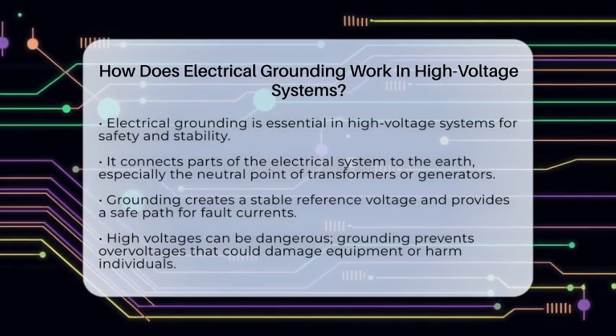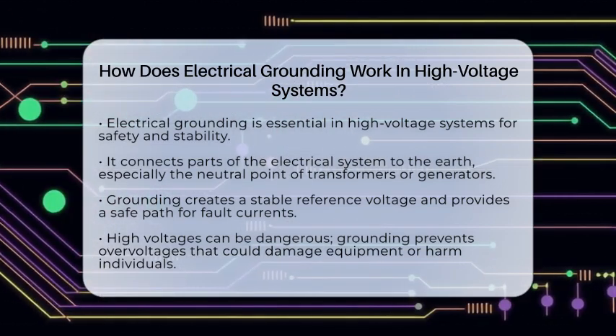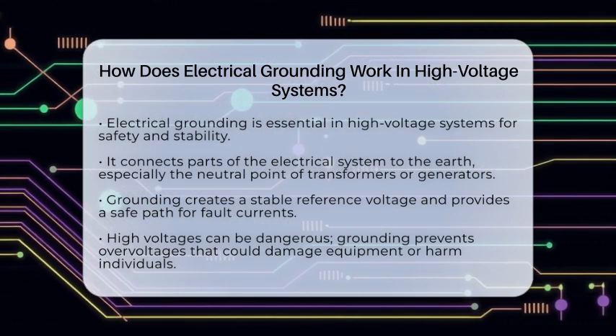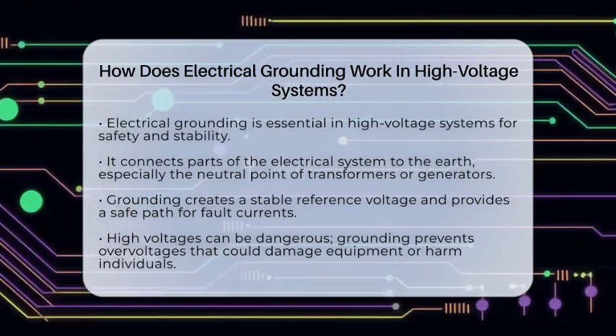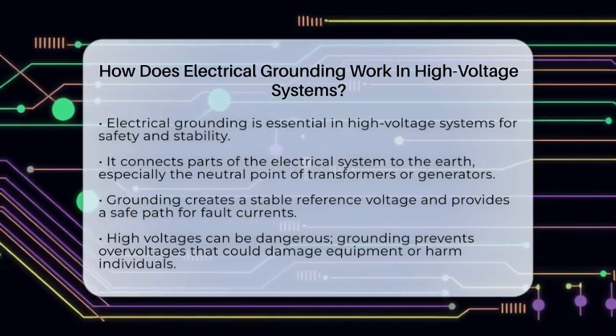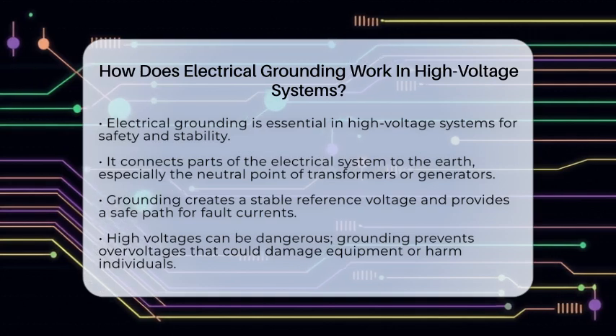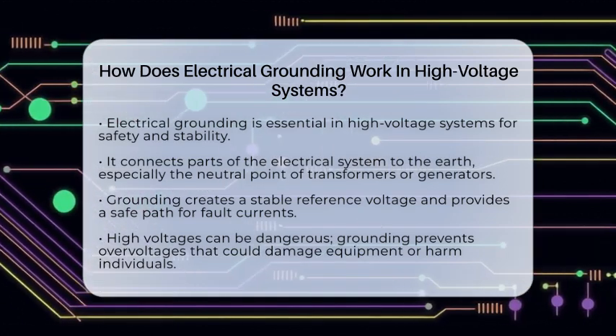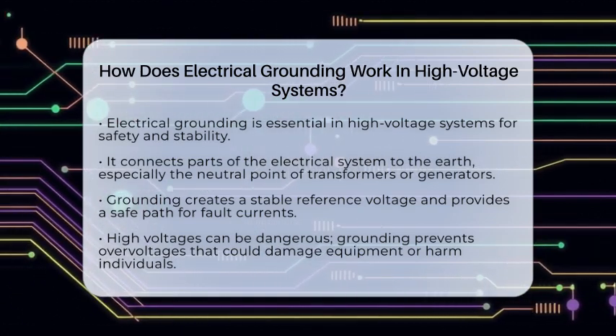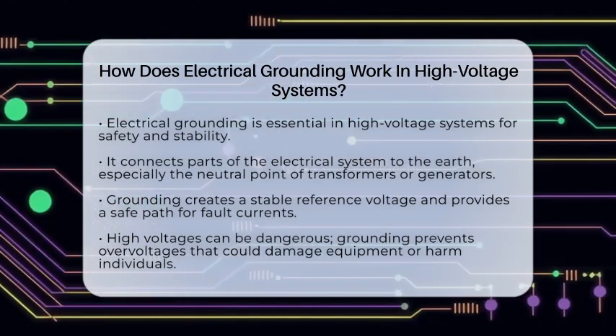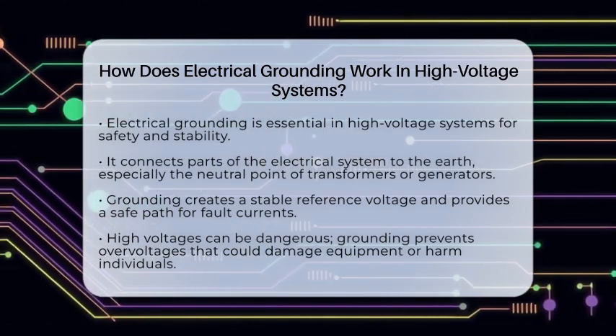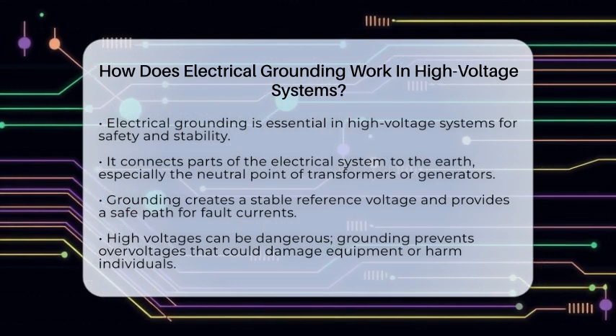Electrical grounding involves connecting parts of an electrical system to the earth. This connection is especially important for the neutral point of transformers or generators. By doing this, we create a stable reference voltage and a safe path for fault currents. This helps protect equipment, stabilize voltages, and keep people safe from electric shock.